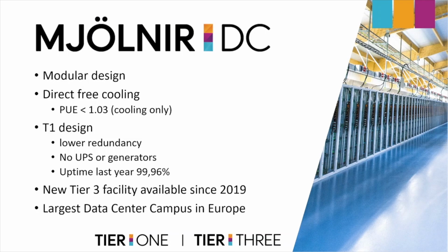Here's an overview and more information about our Mjölnir data center. We build everything in modular fashion, so we can design the setup according to our clients' wishes. With our direct free cooling, we have achieved a PUE of 1.03. In our Tier 1 design, we have a lower redundancy to reduce the cost, which is perfectly suited for crypto operations. There we have no UPS or generators. The uptime in 2019 was 99.96.